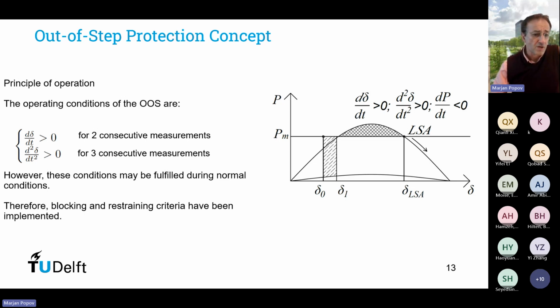The operating conditions for the out-of-step protection are that angular speed and angular acceleration are positive for 2 and 3 consecutive measurements. However, these conditions may also be fulfilled during normal conditions. So, which means that these are important, however, they are not sufficient. Therefore, blocking and restraining criteria need to be implemented depending on the circumstances.